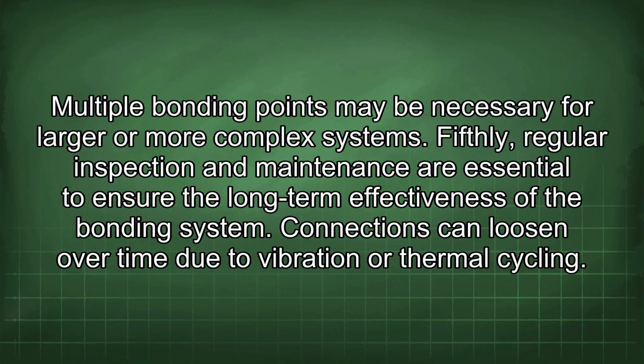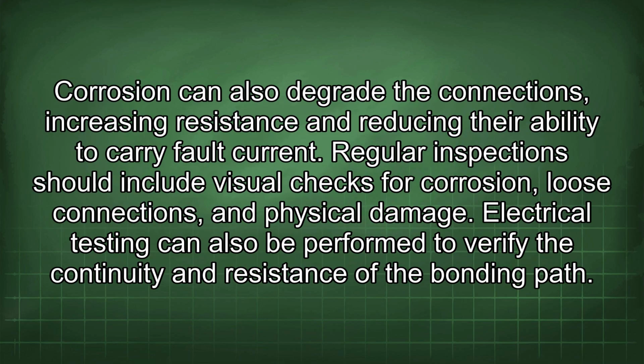Fifthly, regular inspection and maintenance are essential to ensure the long-term effectiveness of the bonding system. Connections can loosen over time due to vibration or thermal cycling. Corrosion can also degrade the connections, increasing resistance and reducing their ability to carry fault current. Regular inspections should include visual checks for corrosion, loose connections, and physical damage. Electrical testing can also be performed to verify the continuity and resistance of the bonding path.